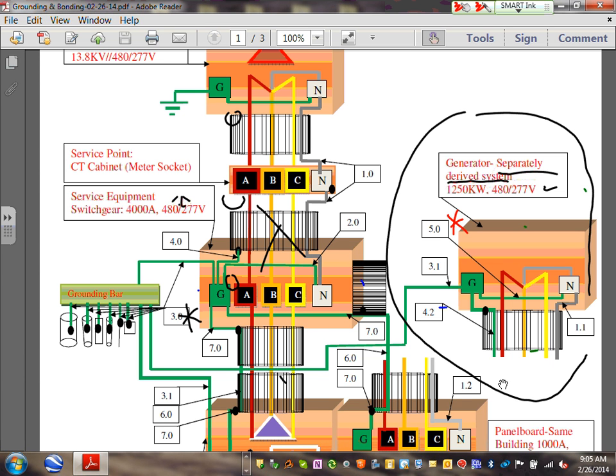So, for a separately derived system transformer, we go right inside the generator and we bond the neutral to the ground. Then we have to take a grounding electrode conductor to the grounding electrode system in the building. Then you have to take something called the supply side bonding jumper, which may take you from the generator to the first disconnect or the first overcurrent device. The last thing you need to do is size the neutral.